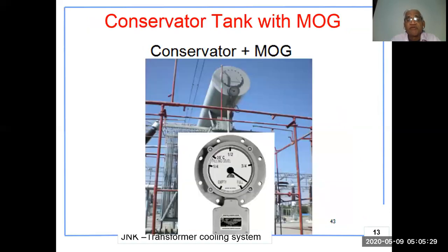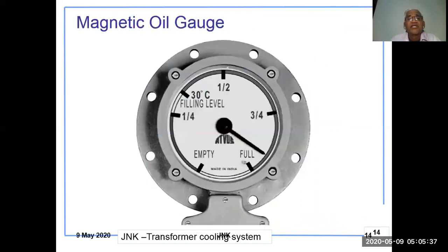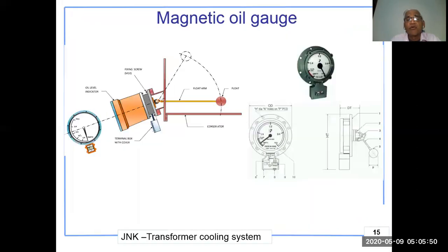Here you can see a conservator tank with a magnetic oil gauge (MOG) fitted on it. The MOG offers the advantage that the connection between the oil and the meter is not direct — it works through a magnetic mechanism — and this is how the magnetic oil gauge is fixed onto the conservator, so there is no oil leakage.